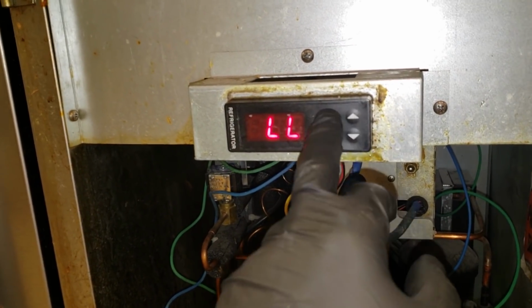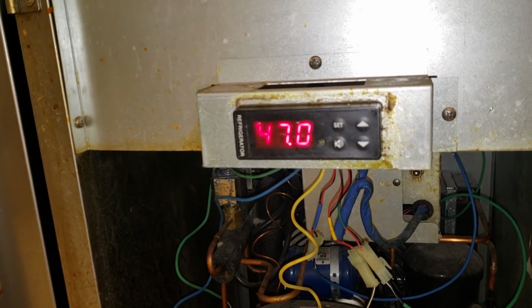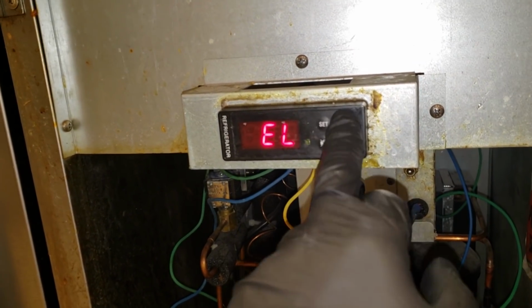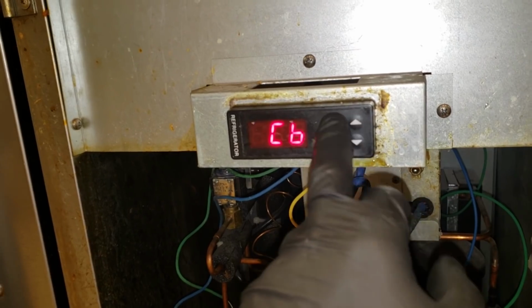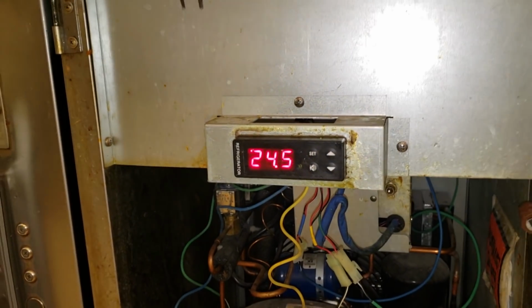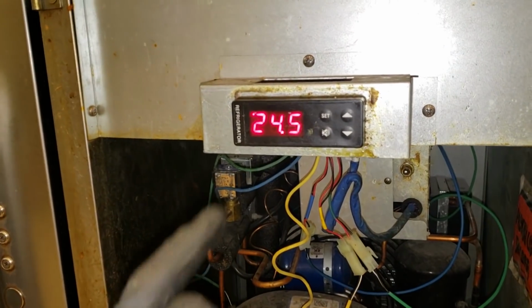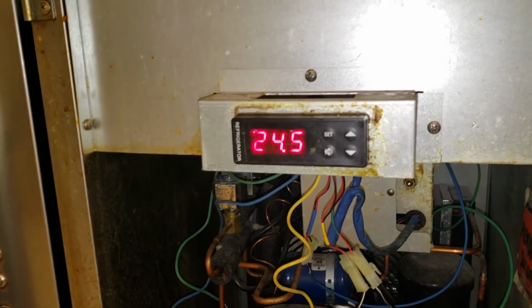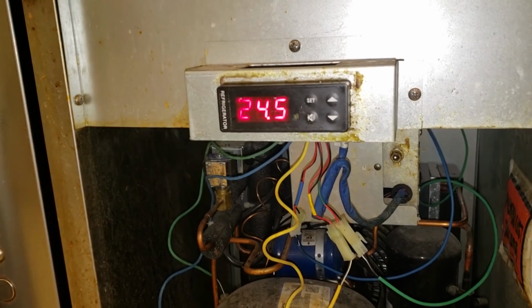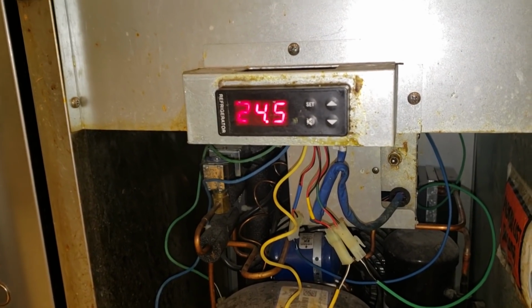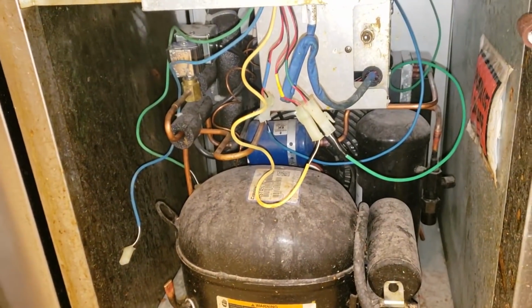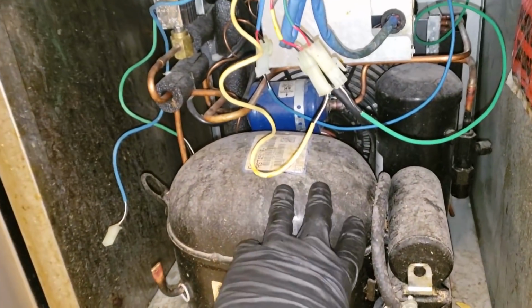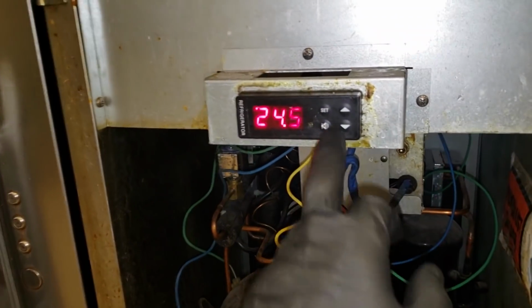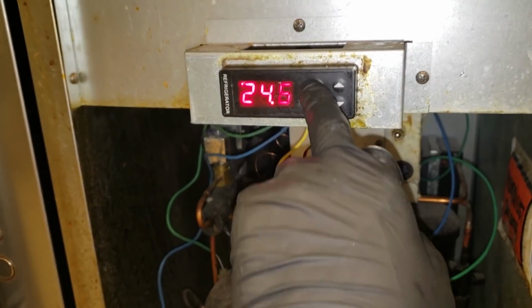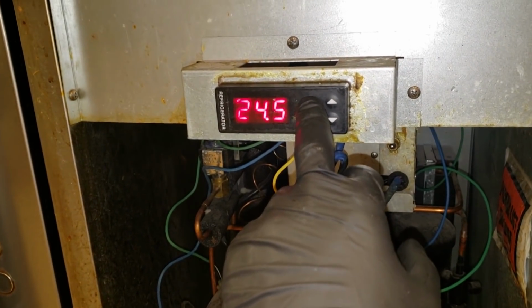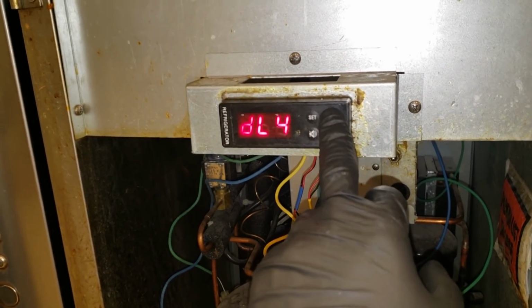So if we go up here, LL is that yellow sensor, 47. EL is 23, CB is 24. So what they're going to do is shut off the compressor because the glycol temperature is 24 degrees. They're just going to let the glycol circulate through there and bring the box temp down. So see, there's no need for the compressor to run because our glycol's still at 24 degrees. So it's still nice and cold in there.